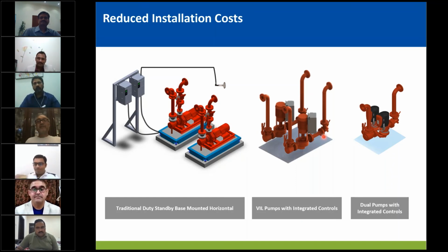And to directly answer that question, if you want to replace a motor, in most cases it is an industry standard motor. An induction motor is a standard frame size. You can replace the motor, you can service the motor locally. There are no problems most of the time. And variable speed drives as well, most of the time they are available. What you will be missing is, once the controller fails, if you don't buy from the manufacturer, the program is not copied over or reprogrammed on that controller. So if you don't use that program again on that controller, you miss the whole opportunity of that energy savings potential.